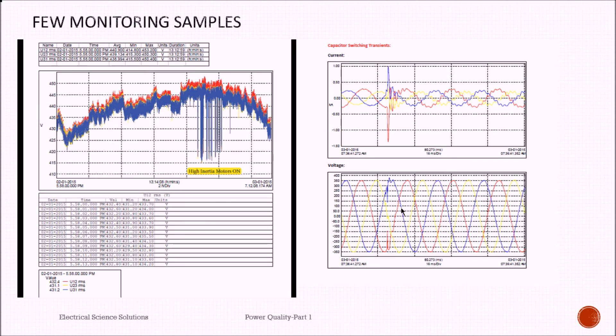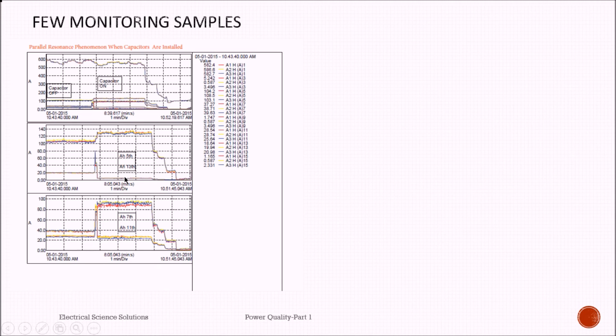Here this is a case of parallel resonance phenomena when capacitors are installed. You can very well see this is a capacitor off region, this is a capacitor on region, and there is an amplification in the particular harmonics. So if you can see fifth harmonics in the capacitor off region, it was in the range of 100, but as soon as you make the capacitor on, it rises up. However, 13th harmonics reduces. So this kind of information that we can get, and then we can provide a solution for this kind of stuff.